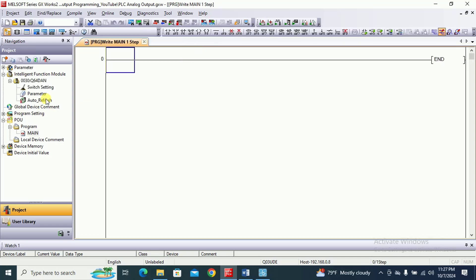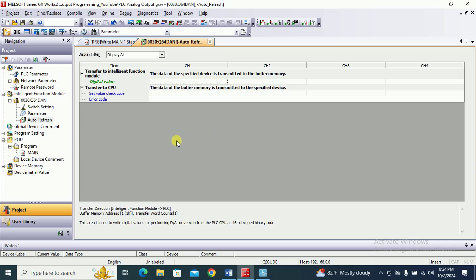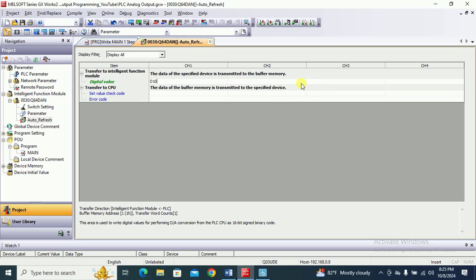Close this window and go to auto refresh settings. Here, for each channel of the analog output module, you can assign a data memory address in the PLC CPU memory. The DA converter will get digital values from this buffer memory address and convert them to analog output signal. Set the data memory address as D10 for channel one, which will store the 16-bit digital value. You can assign addresses for other channels similarly if needed. Leave unused channel areas blank.